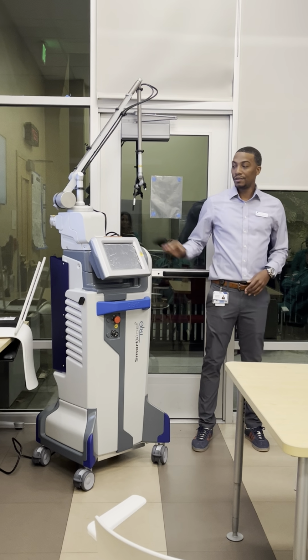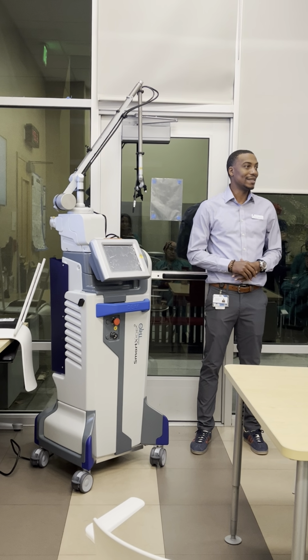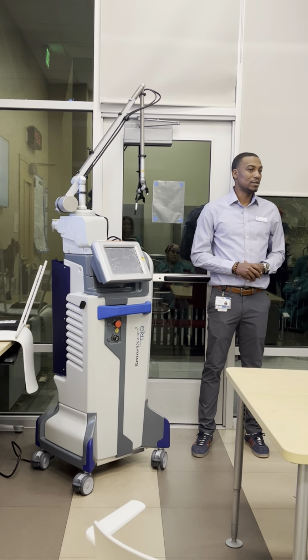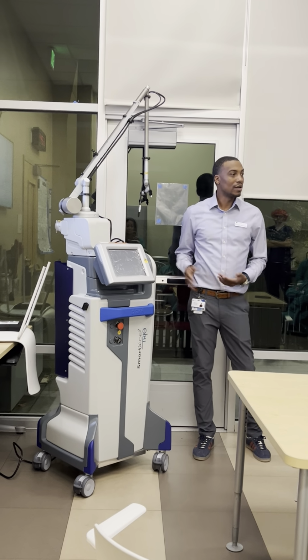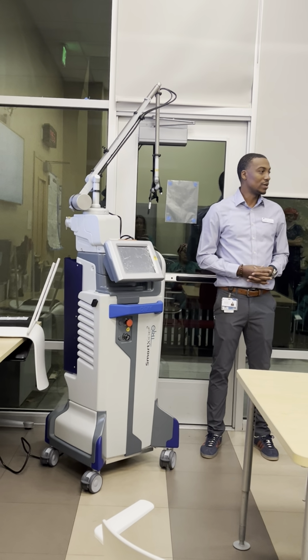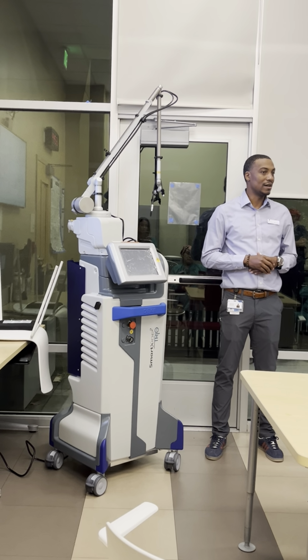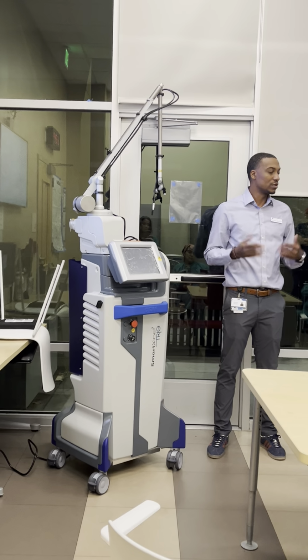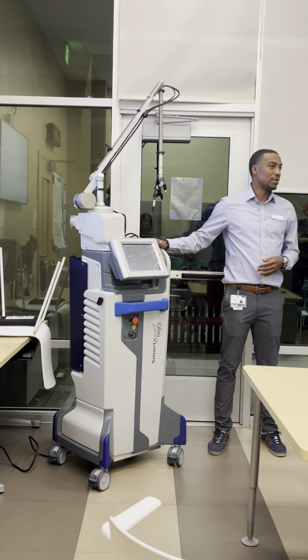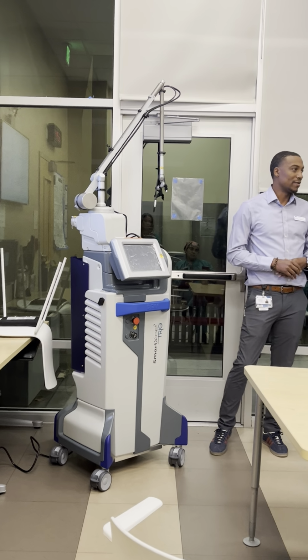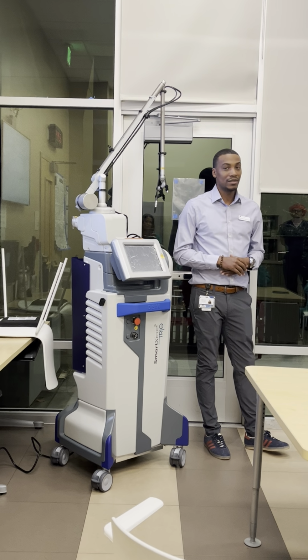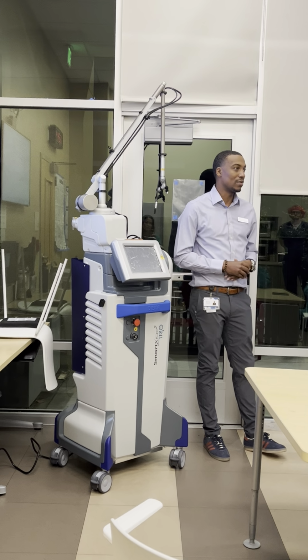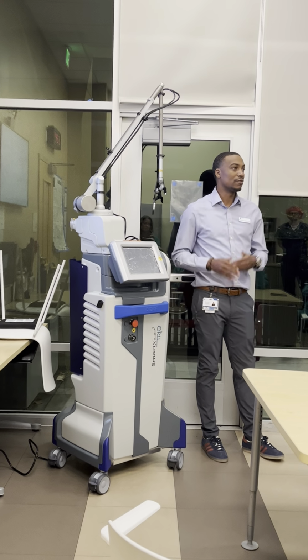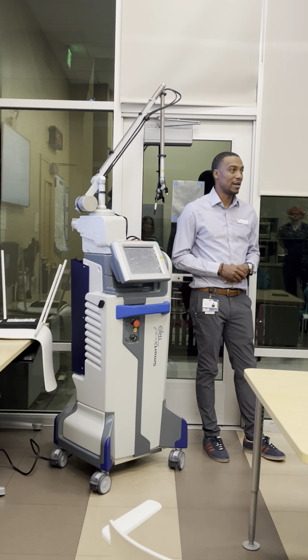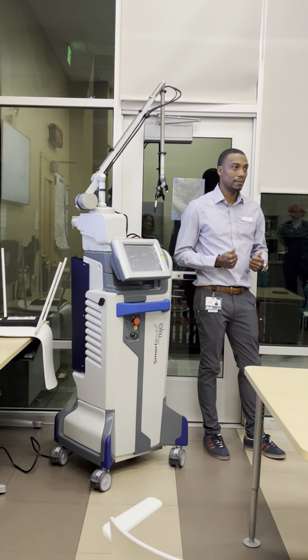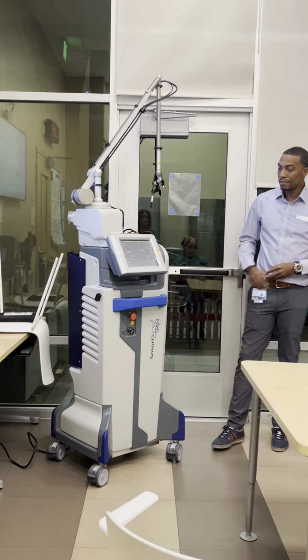Also, do not plug your laser machine into the same outlet the boom or anesthesia is plugged into. The laser has a short, understandably. Most ORs are set up with GFCI circuit breakers. They have their own circuit breakers, but we don't want to do anything that could put the patient at risk. We all advocate for patients in the OR, and this is one of the things we can do to be on the patient's side without them even knowing. So plug into a different plug outside of your anesthesia unit. Good to go.